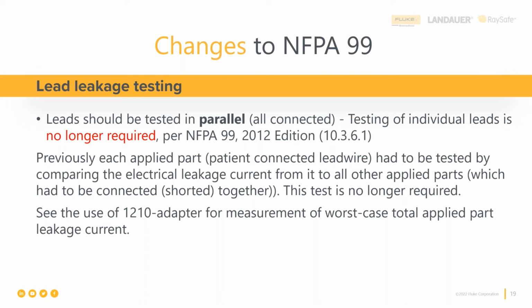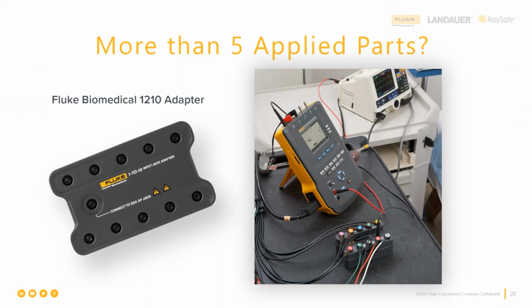And before you go improvise something to help you do that, recognize that we do provide the 1210 adapter that works with all our electrical safety analyzers that have the capability of testing patient connections. So that's the ESA 612, the 614, 615, and ESA 620. And you can use one or more of these depending on how many patient connections need to be tested. This accessory shorts them all together and gives you one test lead coming off of it that you can connect to the lead posts at the top of the analyzer. So we provide, and we're here to help you.